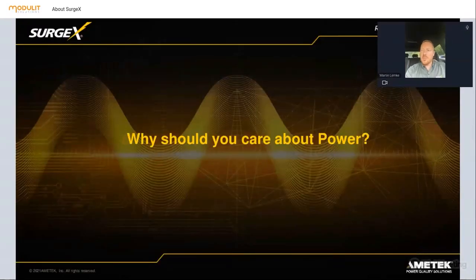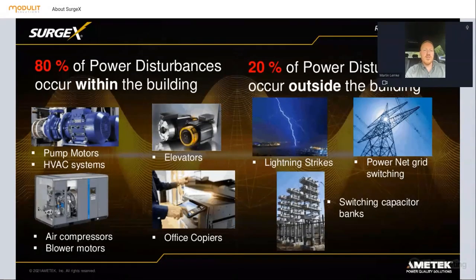So why should we care about power? I'm living in Germany, in the region of Munich, and even there, power quality has gone down over the last years. The problem isn't catastrophic events like a lightning strike or power grid switching - that's only 20% of the problems. 80% occur within the building, whenever there are big inductive loads like elevators or air compressors being switched on, pulling a lot of current, which causes issues.